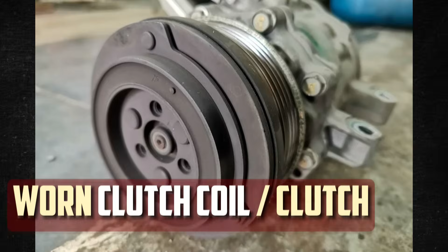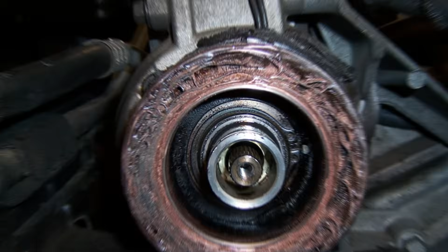Damaged clutch coil or worn clutch. It's possible that it's just worn out, just like any clutch. Older models or those with excessive AC system use are most likely to experience this issue. When it's newer, the clutch won't typically wear out. It is possible that the clutch will not engage if the clutch plate is worn out. Occasionally, it might also slip, resulting in unpredictable operations. To further increase the clutch's lifespan, some air conditioning clutches have spacer shims that can be taken out.